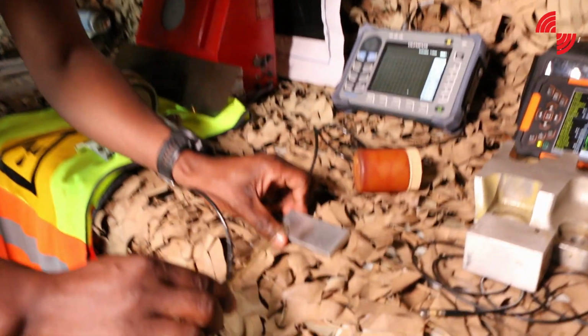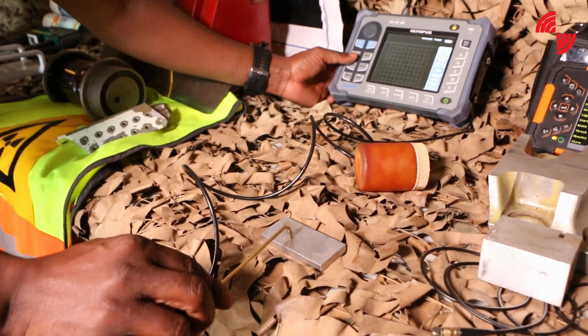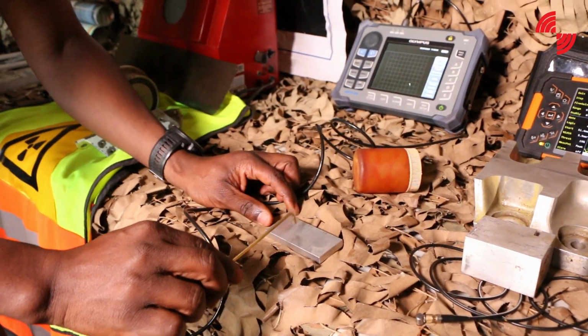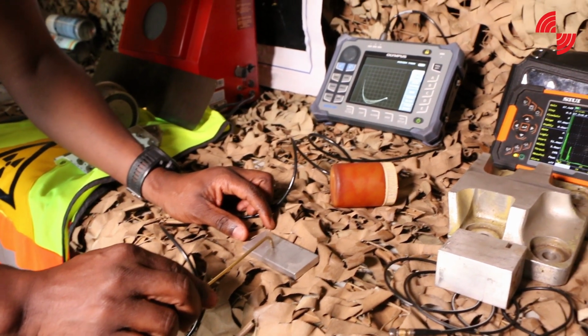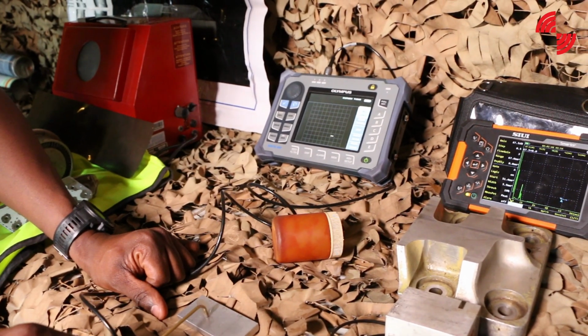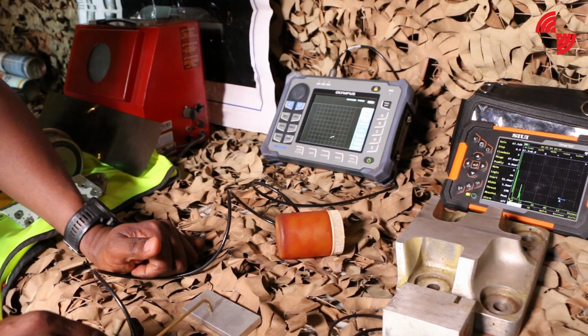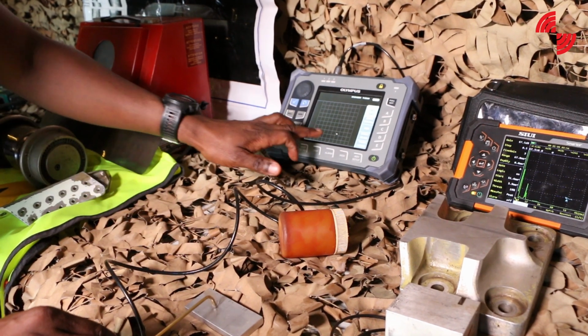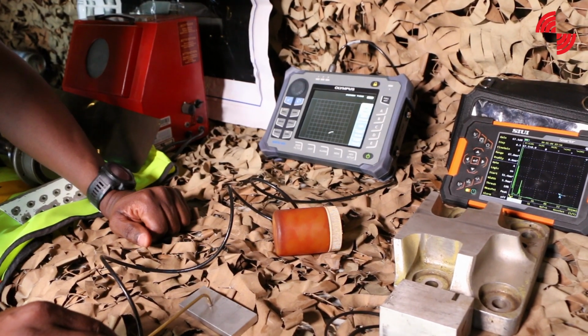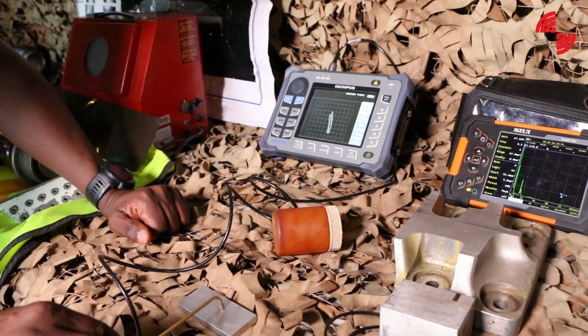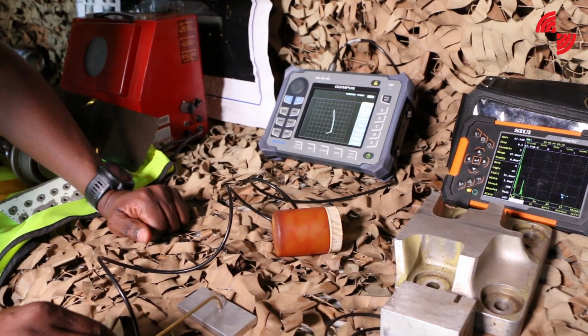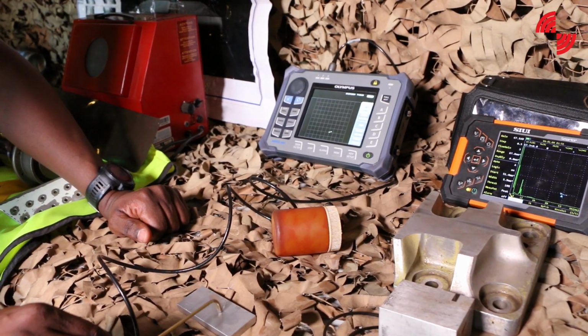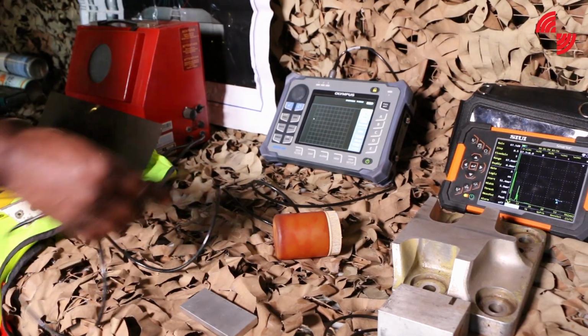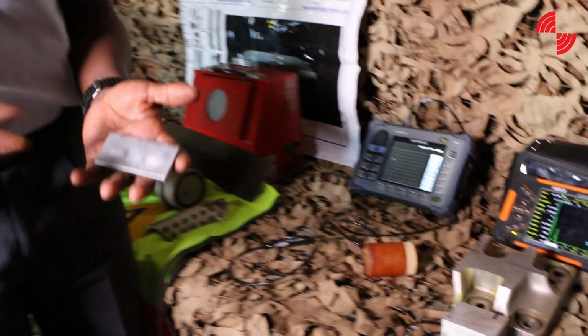If we go live and you focus on the screen, I'm going to null my screen, and then I can see my dot appearing. Then you will be scanning. As I'm scanning, you can see there's nothing. If it appears that way, it means there's no defect. But as soon as I go over the crack, you can see on my screen a very big pulse that goes high. Then it tells me that on my component, there's an indication or a crack.